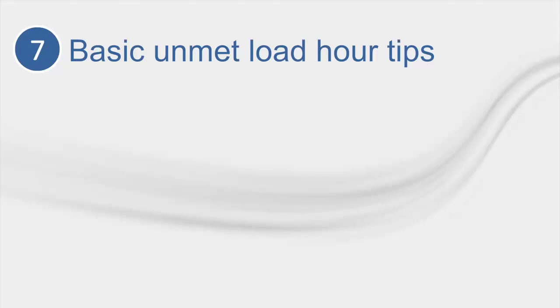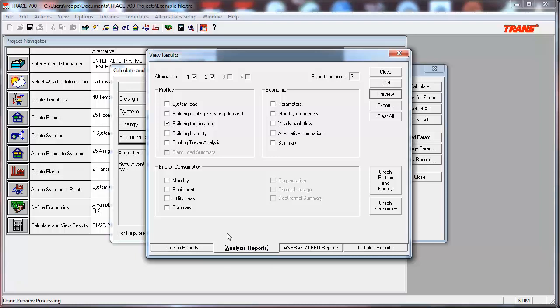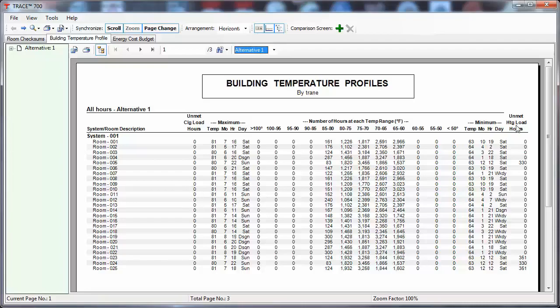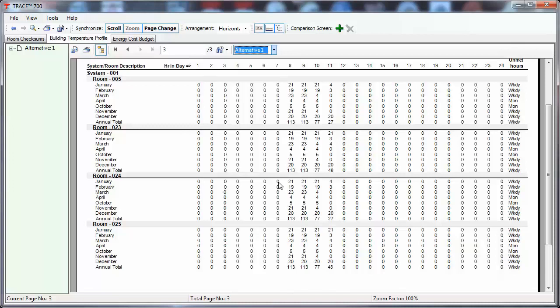For tip number seven, we will talk about unmet load hours. One of the biggest things to know about unmet load hours is where to look for clues that will help you resolve them. The Building Temperature Profile Report is generally a great place to start. This report will show you how many unmet heating hours and unmet cooling hours are in each room. It will also tell you when those unmet load hours occur during the day, as well as what day type. This is important because it leads you to different conclusions for the cause of the unmet load hours. For instance, if all your unmet load hours are happening at 8am, then maybe you need to include morning warm-up as a control strategy.